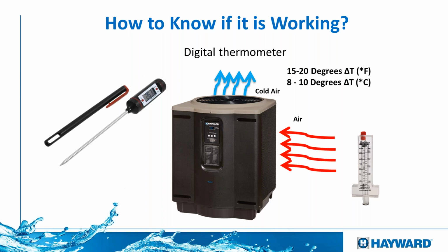So what do you do with this test? All you've got to do is stand right next to the heat pump on the side and put a thermometer right next to it on the bottom or on the side of the heat pump, not on top. Take that reading, and then after that, you place the thermometer on top when the heat pump is running, exactly where you feel that cold air, and you take that temperature reading. You have to have a differential of 15 to 20 degrees Fahrenheit or 8 to 10 Celsius. If you have that, that means the heat pump is working at its full capacity, at the best you can get out of it.